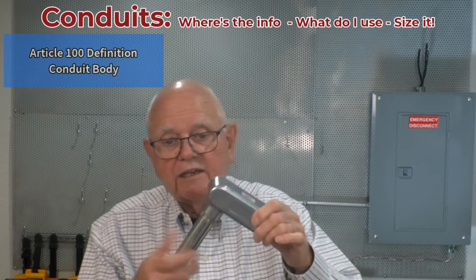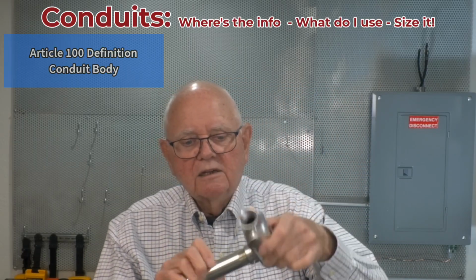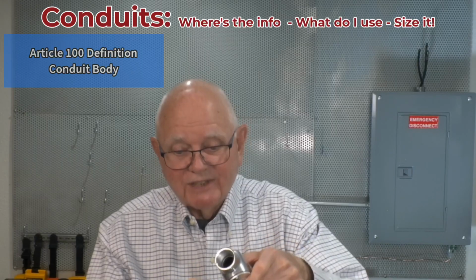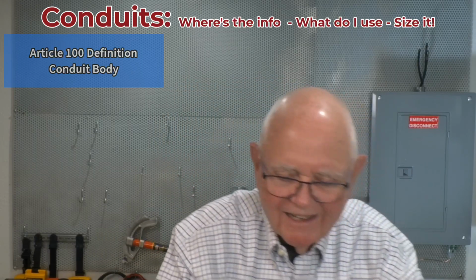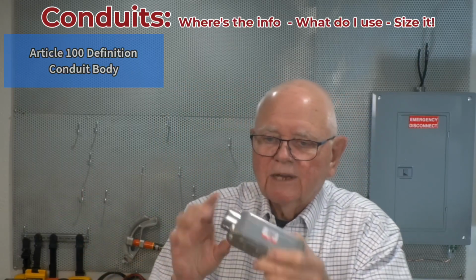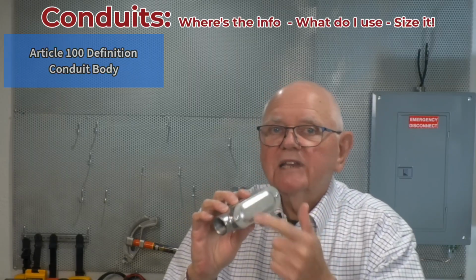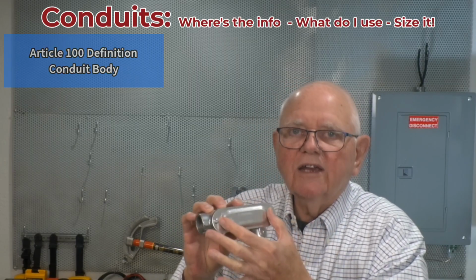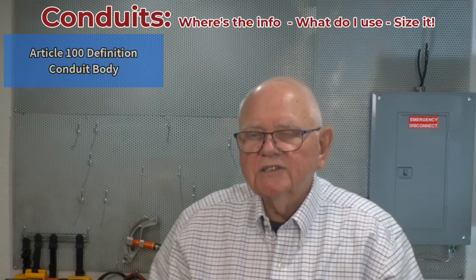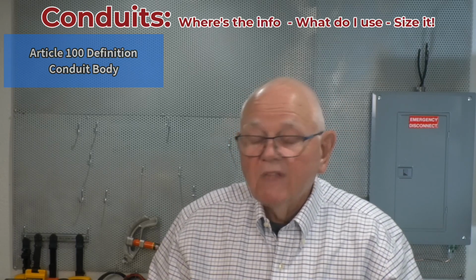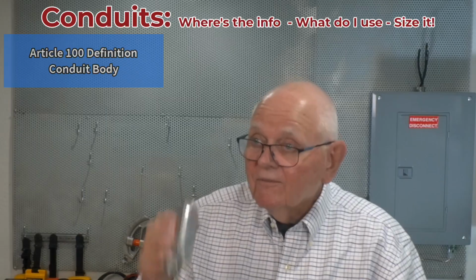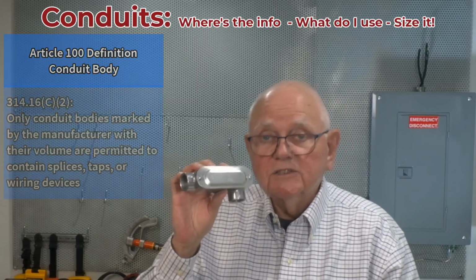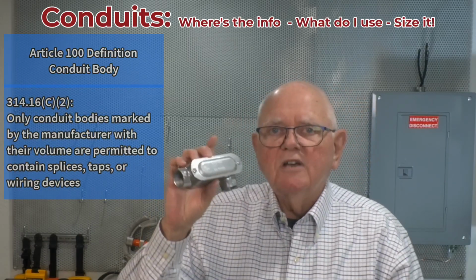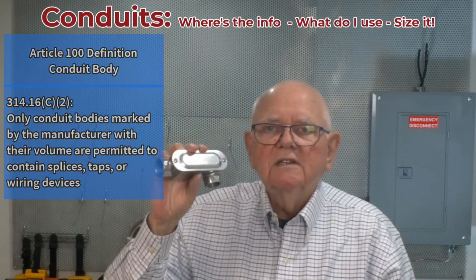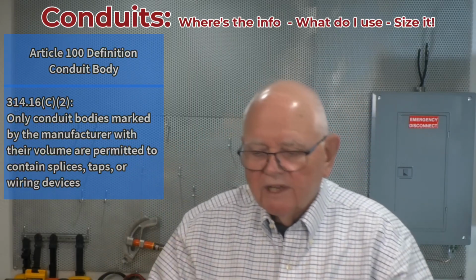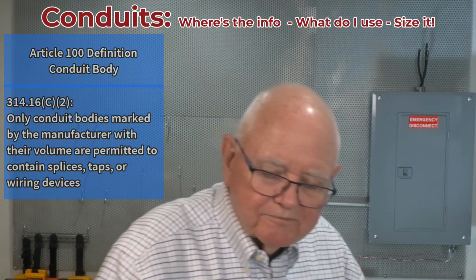So I can take this conduit body, this LL, off, separate from the conduit, and the key is it has a cover on it. So I can pull the cover off and access my conductors on the inside. That can be handy. If I have the volume marked in here, which is pretty typical, I'm also allowed to splice inside of this conduit body. But once again, there are other requirements in the code.